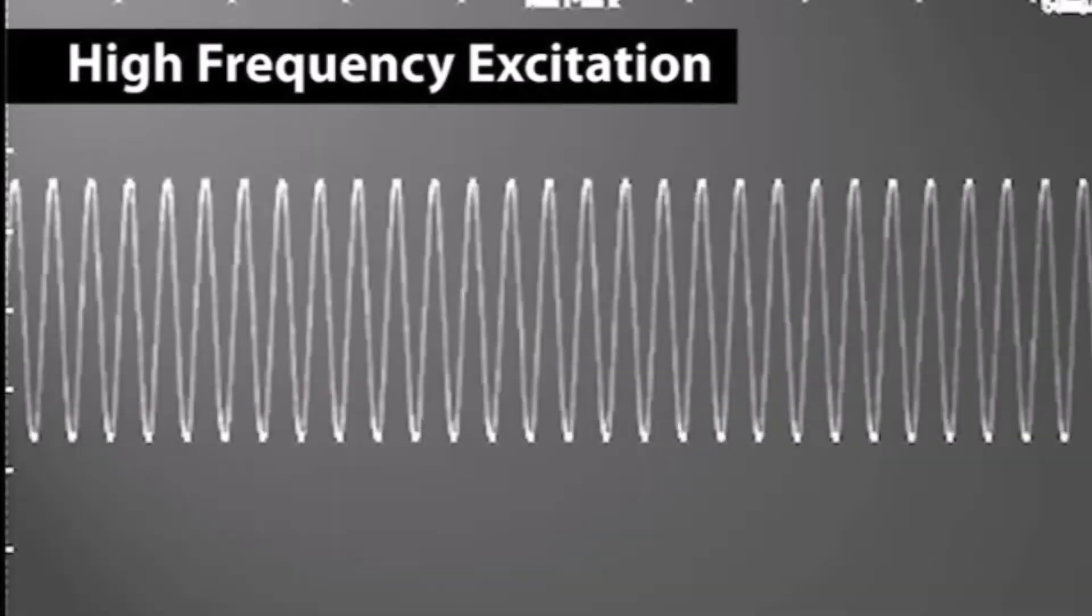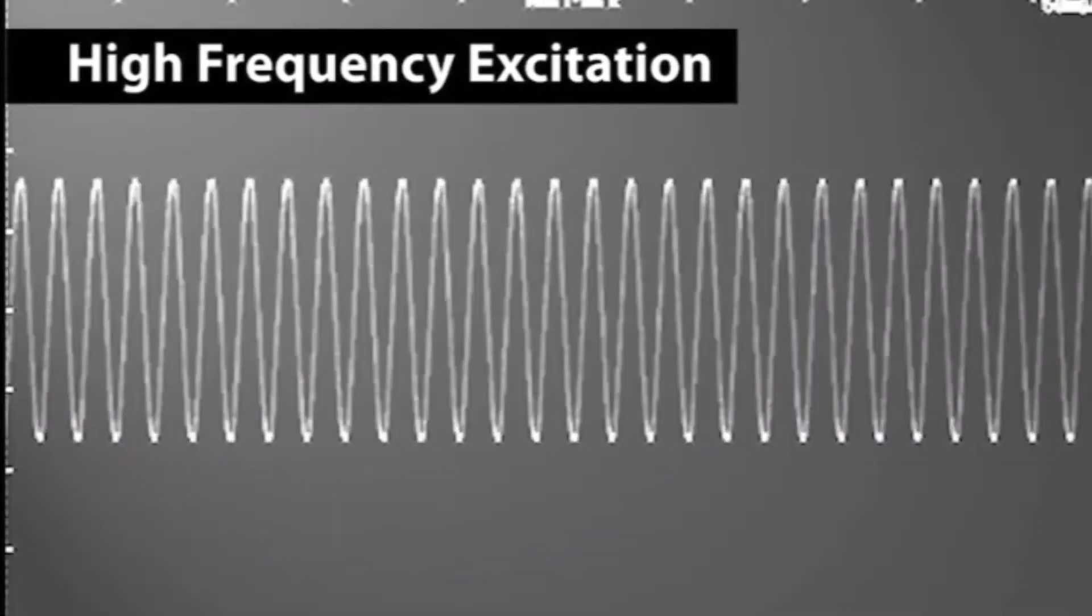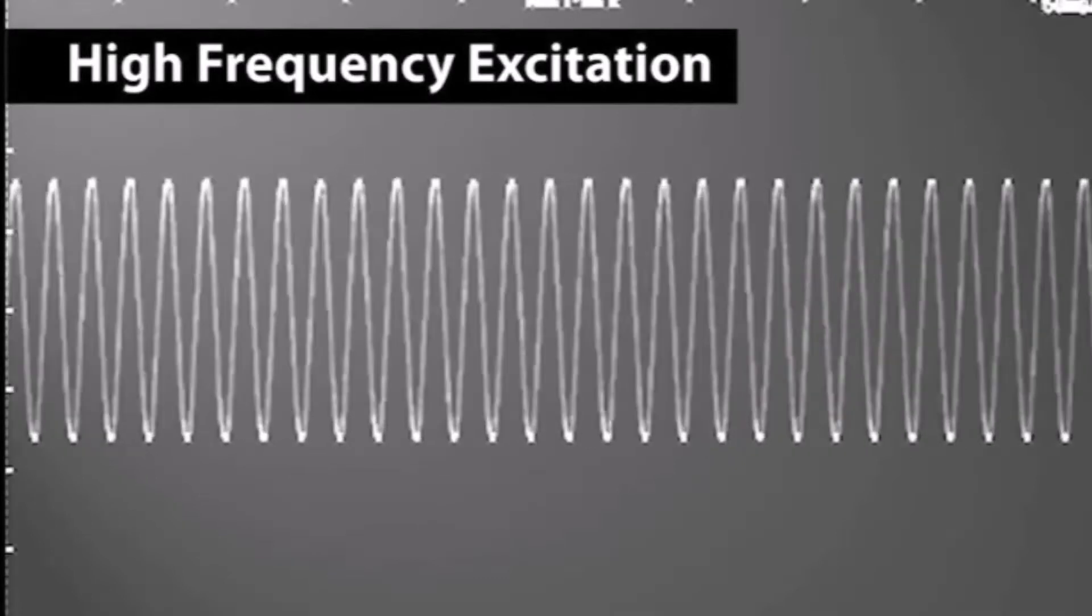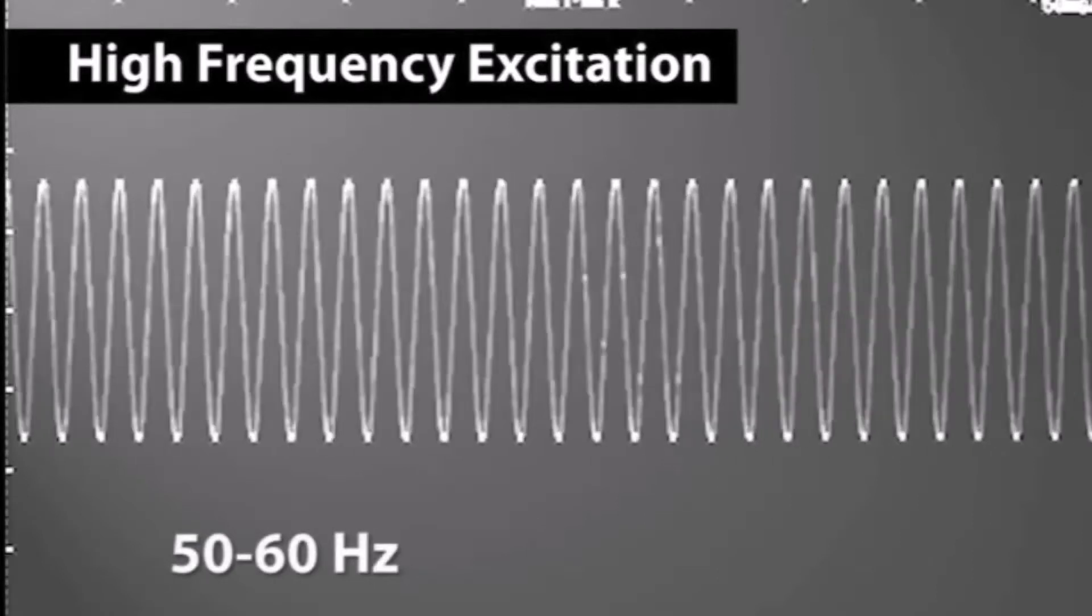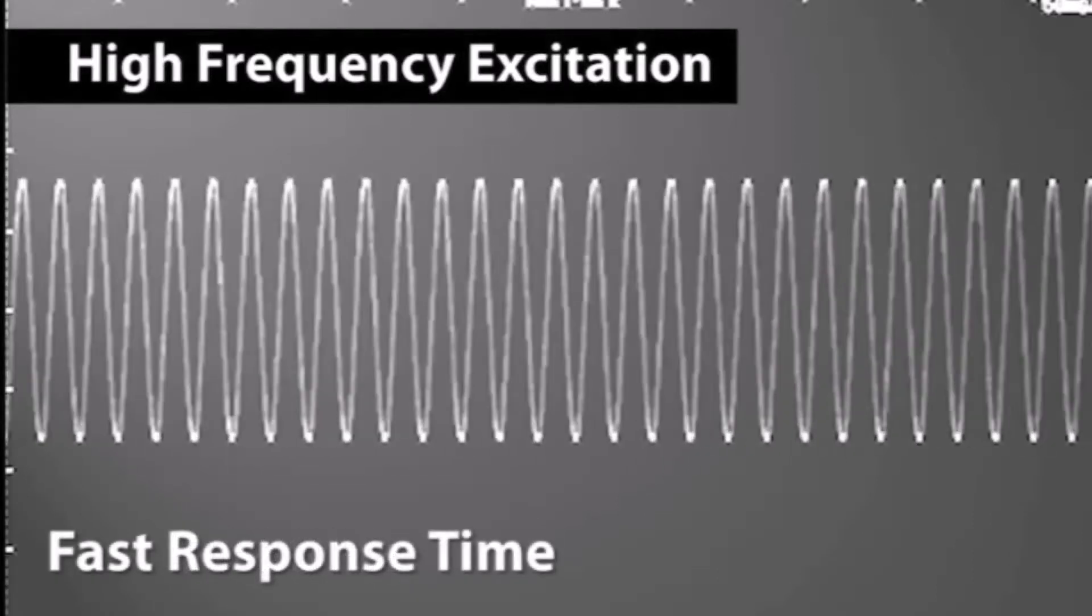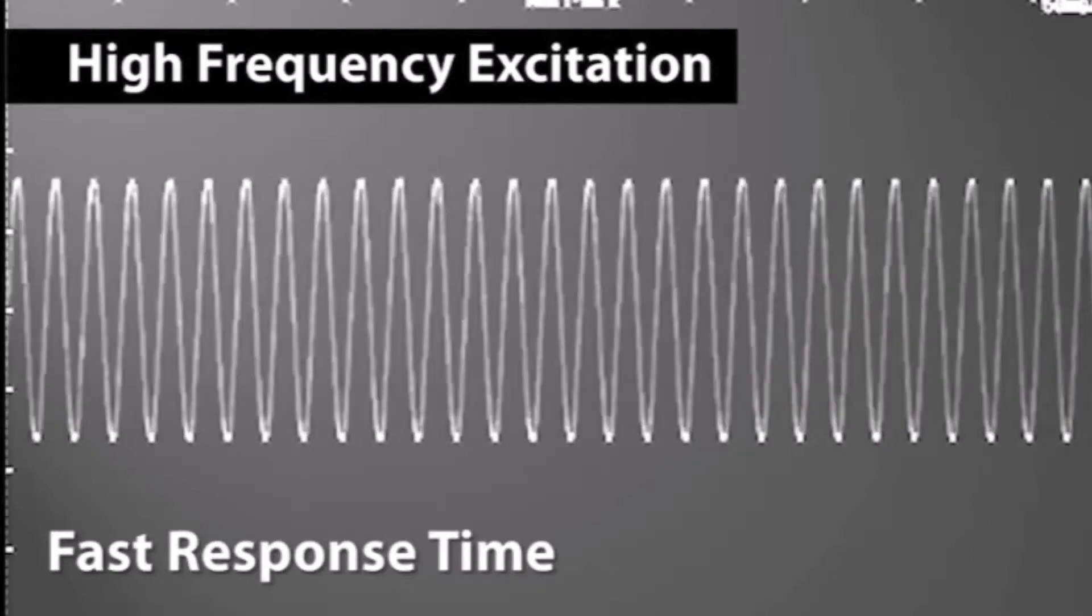When magnetic flow meters were originally designed over 50 years ago, they utilized AC-type excitation. AC-powered magnetic flow meters use line frequency to generate the magnetic field. The frequency of AC excitation is typically 50 to 60 hertz. This type of excitation has a very fast response time, making it suitable for slurry applications.